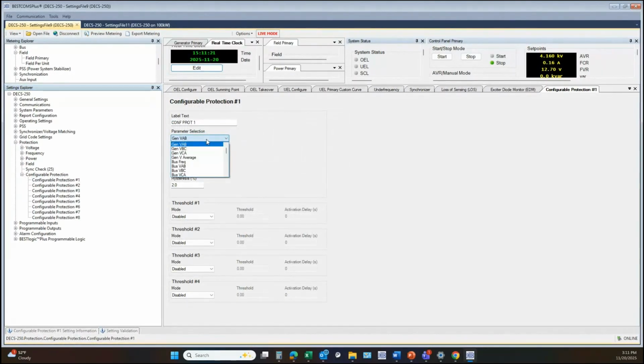Configurable protection allows you to select from a list of options to monitor, and then define thresholds for that. This can be used for having the DECS give itself a start or a stop. If it senses your residual voltage or your PMG voltage getting up above a certain level, it knows your machine is started, and it can sense that. You can use this threshold in an overstate and then use this in logic to trigger a start. So that can be done. There are also ways to set up the configurable protection for synchronous motor applications, so you know when to transition from manual control to automatic control.